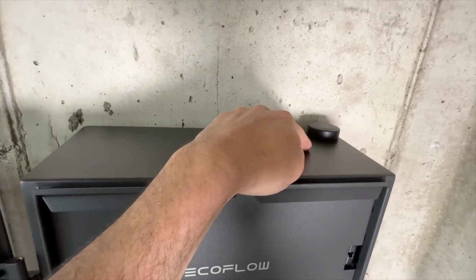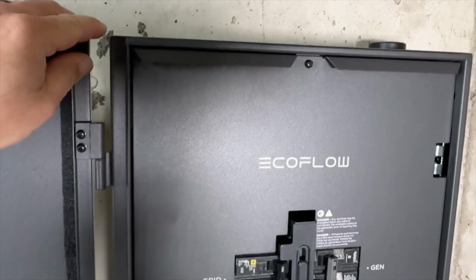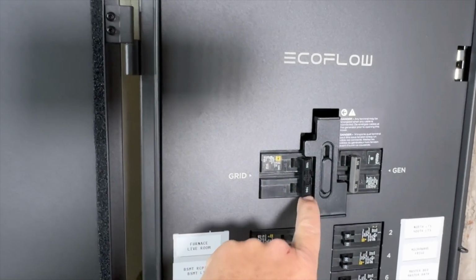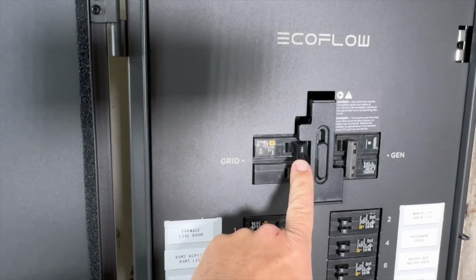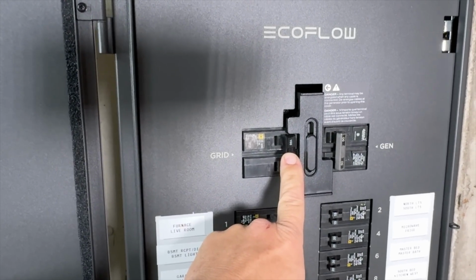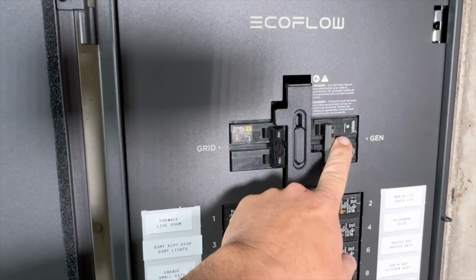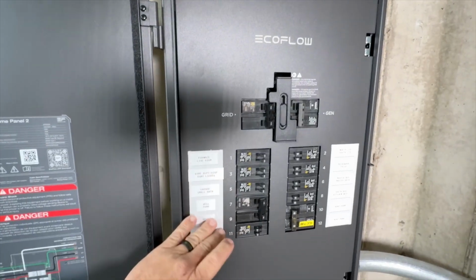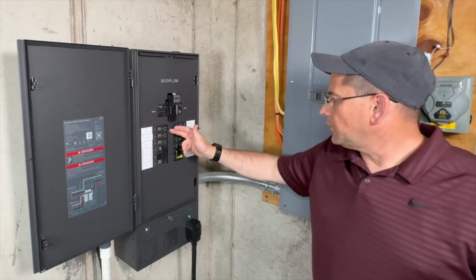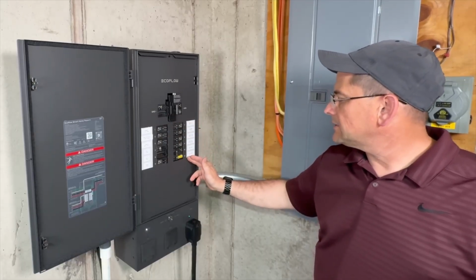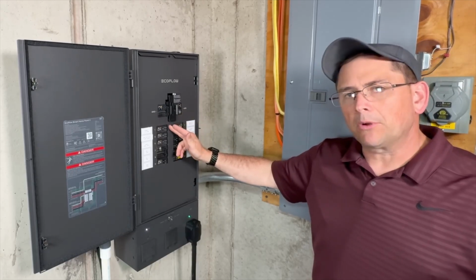Now up here on top is the Wi-Fi antenna. Coming right down to here, we have our interlock switch. So this is the 100 amp circuit that I have coming into the transfer panel from the main breaker panel. This is my 50 amp supply from the generator. And here are my circuits for the house. Now, EcoFlow provides you a total of 12 spaces here in this box, which I ended up using tandem breakers.